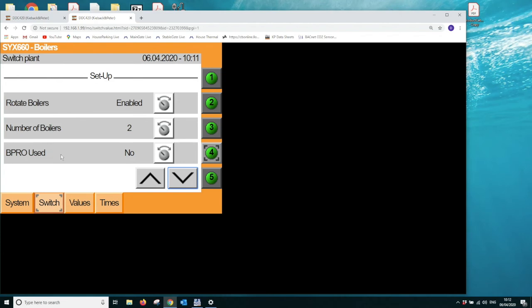Boiler Pro used. Now the BPRO is a sequence module which utilizes the 0 to 10 volt signal. If we use a BPRO, then we need to be sensitive about how the voltage levels work on the 0 to 10 volt ramp, because the BPRO becomes active above a certain voltage range. So we need to make sure that we are able to drop below that voltage range and turn off the Boiler Pro. So when we select no, then we could use that 0 to 10 volt signal for other purposes.